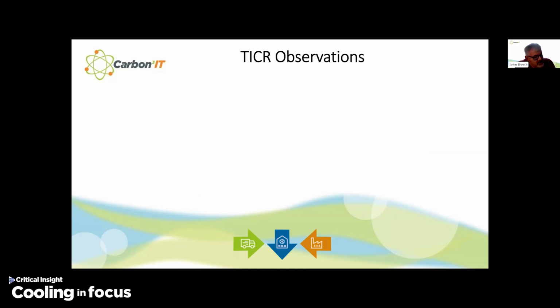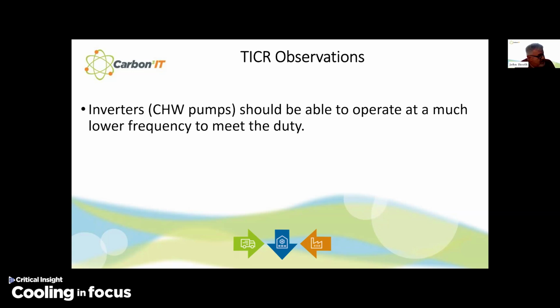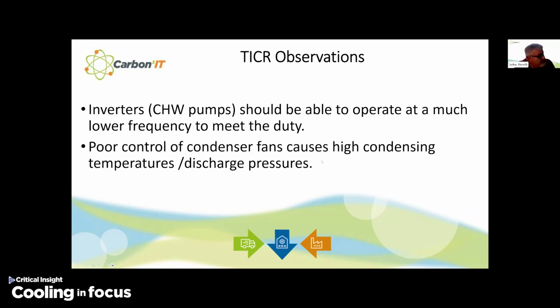Our observations on our surveys, albeit limited, but I cannot believe that this is any different in other server rooms and data centers around the country. We found that the inverters for the chilled water pumps should be able to operate at a much lower frequency to meet the duty. We found poor control of condensing fans, which causes high condensing discharge temperatures and pressures. We found dirty condenser coils.